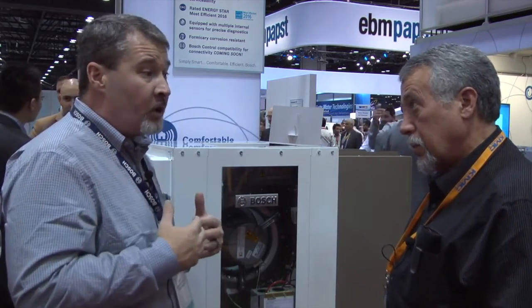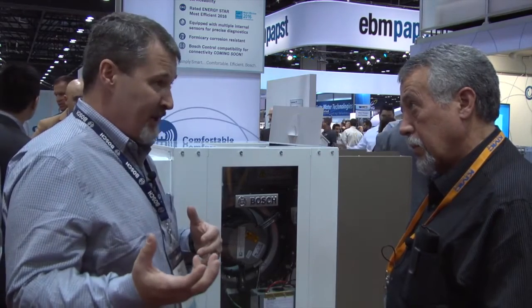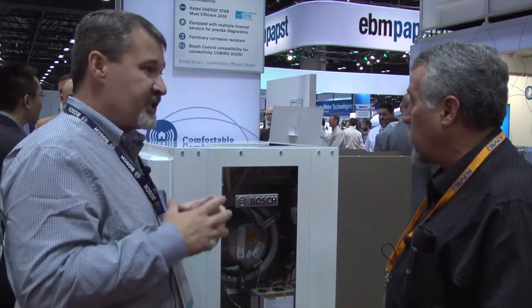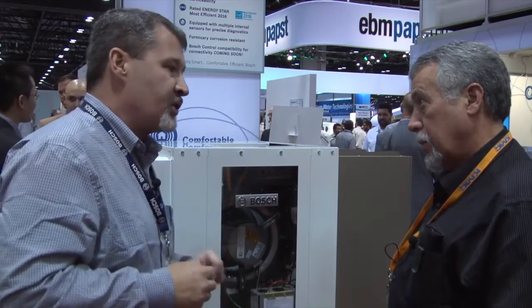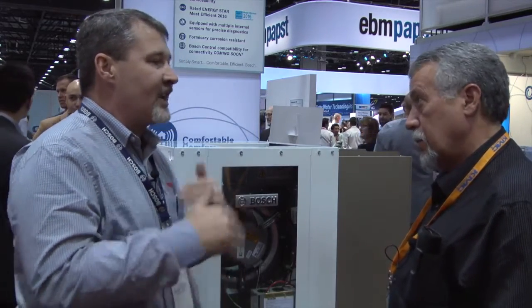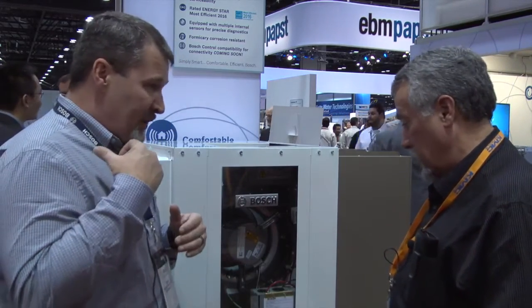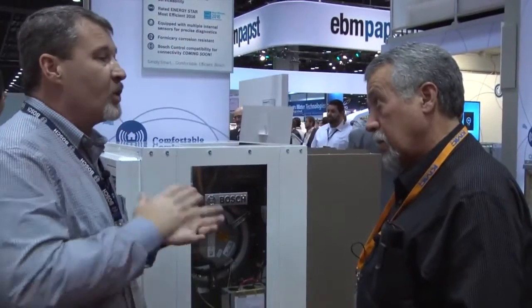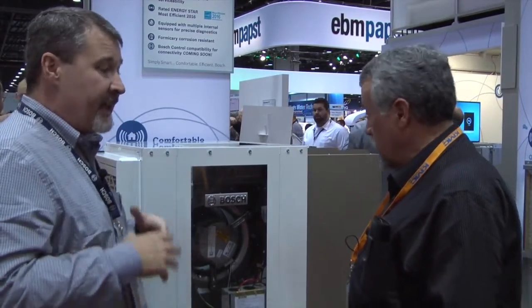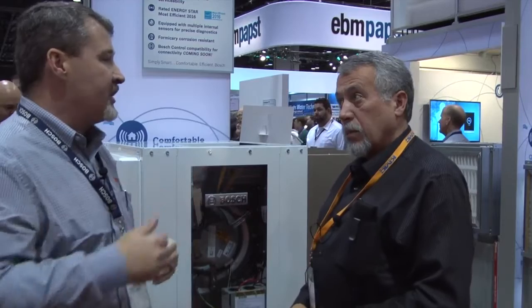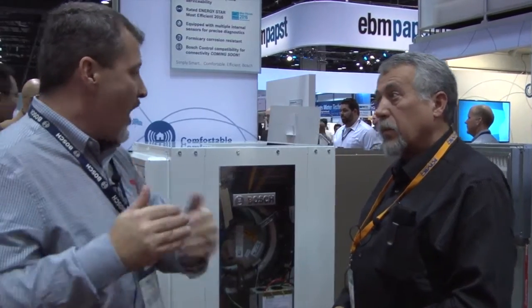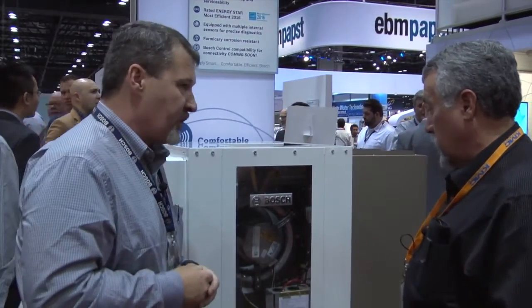We can actually steal heat from the water heater we're trying to heat, because the water heater is actually warmer than the refrigerant temperature. This unit will constantly sample, and when it finds that the water in the water heater is warmer than the refrigerant temperature, it'll shut off. Then it'll come back and resample after 15 minutes to see where it is now, so we can maximize the desuperheater operation.